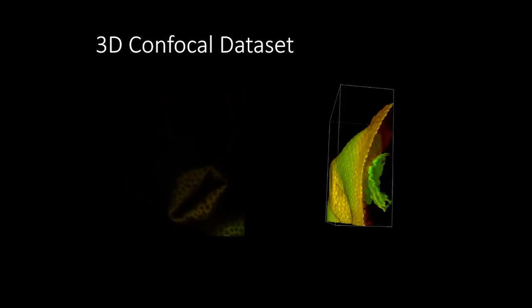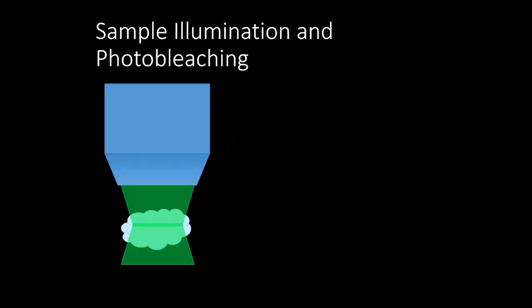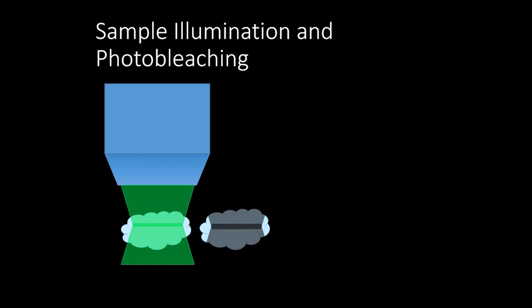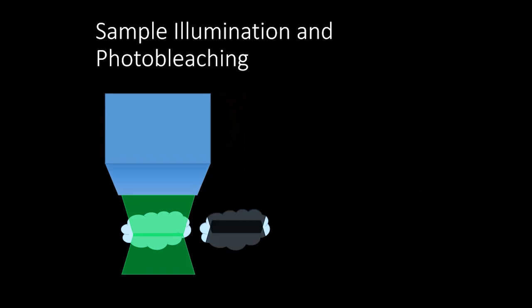One important point: when it comes to photobleaching and photodamage, confocal and widefield are the same — you're illuminating everything in both cases, and the pinhole only cuts out-of-focus light upstream of the detector. In confocal, you're likely taking Z-steps, meaning you're actually taking 30, 40, or 50 images, so you may have more photodamage than with a single widefield image.